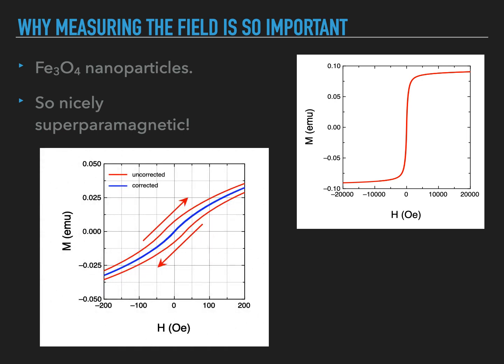Since the aim of having a magnetometer is to characterize magnetic material, the problem of the hysteresis of the superconducting coil that is visible when you try to characterize a paramagnet like palladium seems to be of relatively little importance. But very often, with such kind of magnetometers, you would like to characterize materials that are superparamagnetic, like, for example, magnetite nanoparticles. Superparamagnetism means that the magnetization curve should display several different properties that scale with a certain law with temperature, etc., but the first fingerprint is that the magnetization curve displays no hysteresis.